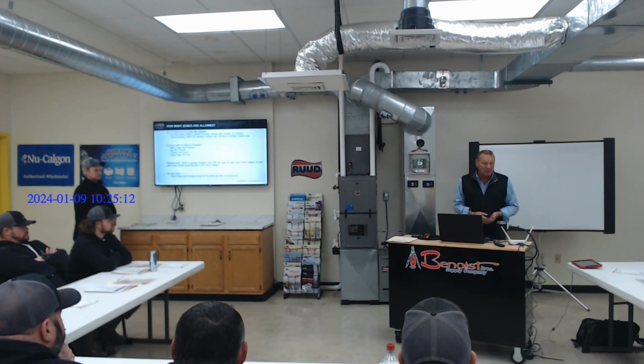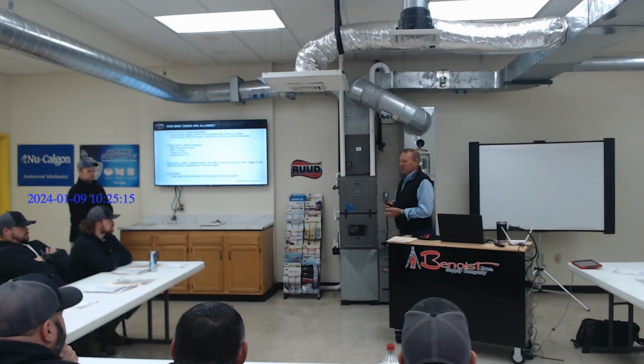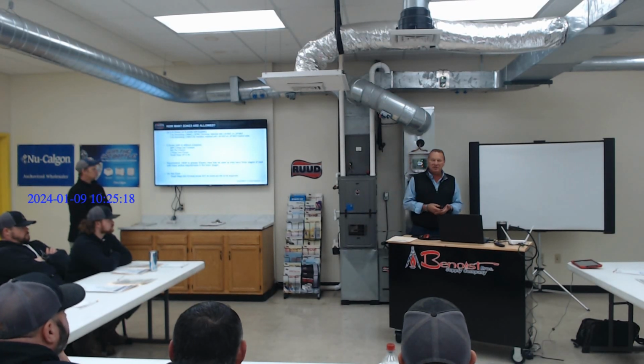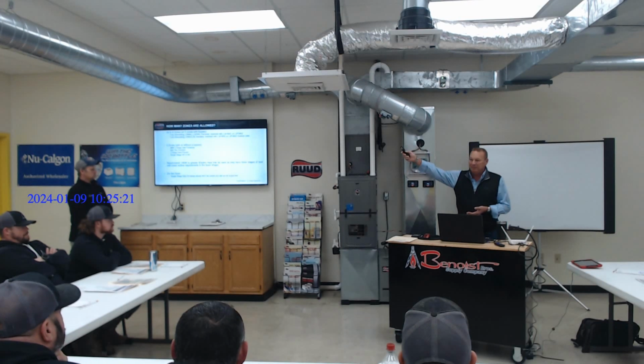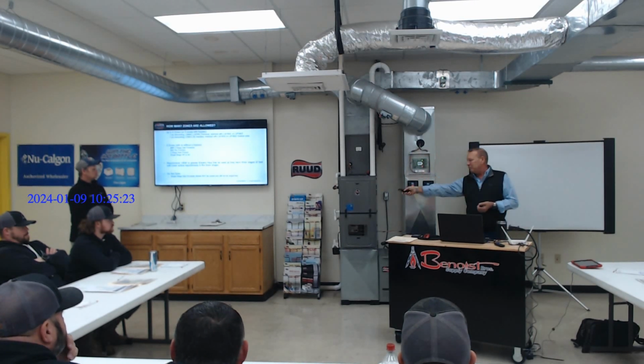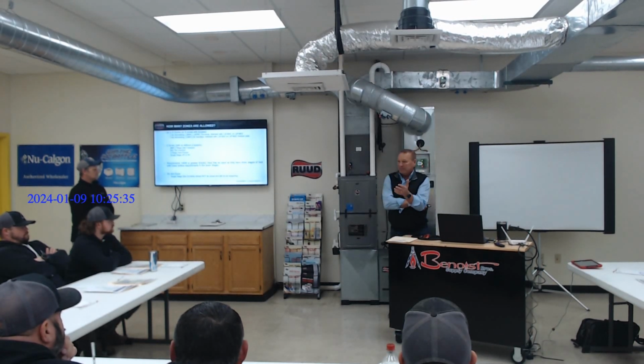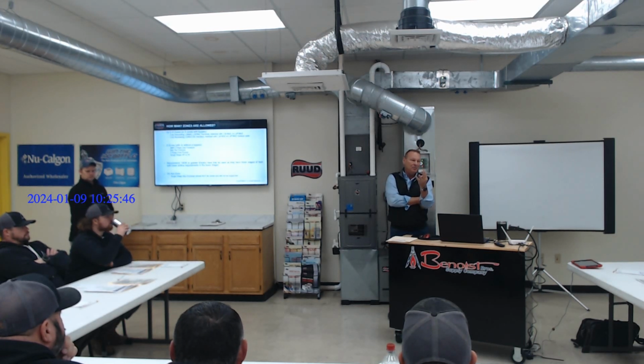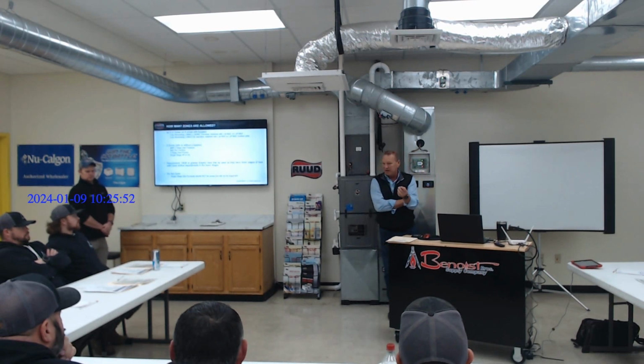And the other thing to remember about the mid-tier product is I need 4 wires to that mid-tier product outside from the furnace, even if I'm using a traditional thermostat, because my outdoor units communicate with my furnace, controlling the blower speeds in my furnace. So my 15 and 16 series, this is a little outside of zoning, but we haven't really done a mid-tier training. Just so you know, I can sell a regular thermostat on a 15 or 16 series product, heat pump or AC. But I have to have 4 wires outside. I have to communicate with the furnace it's hooked up to, or the air handler, because it's got to move the blower speeds up and down from 45% to 75%, and then get it up to 100%.